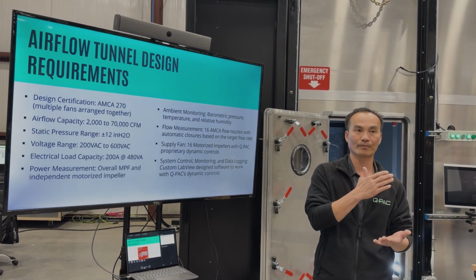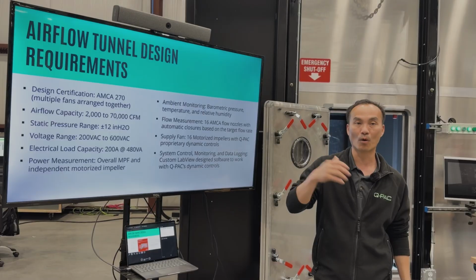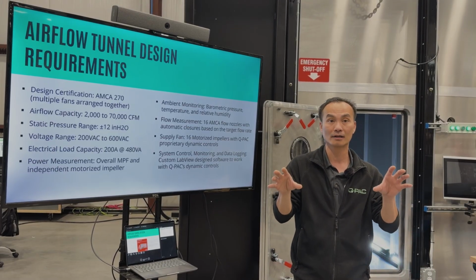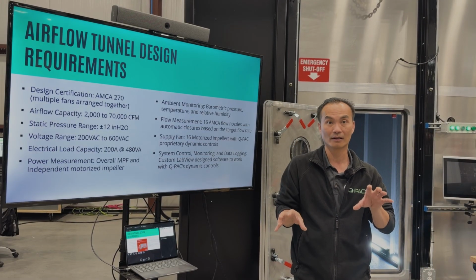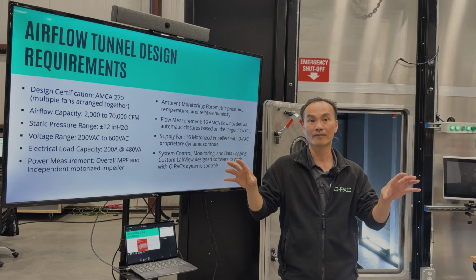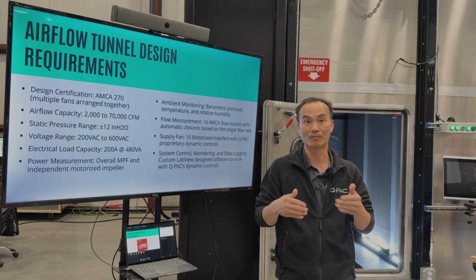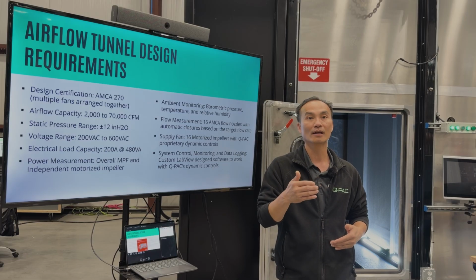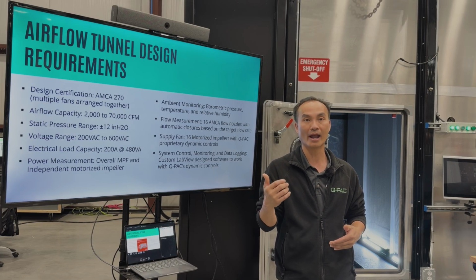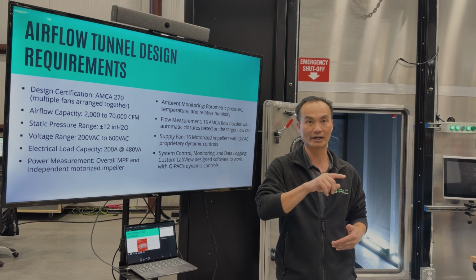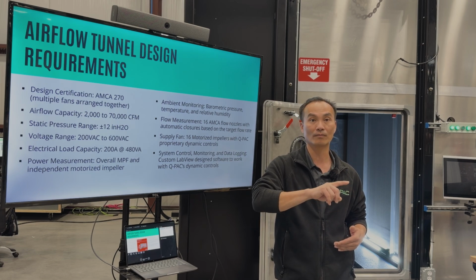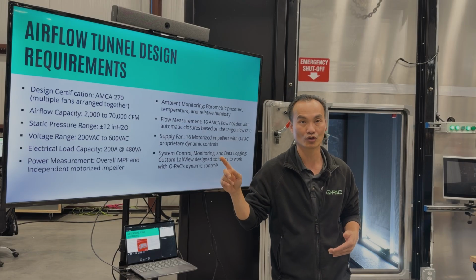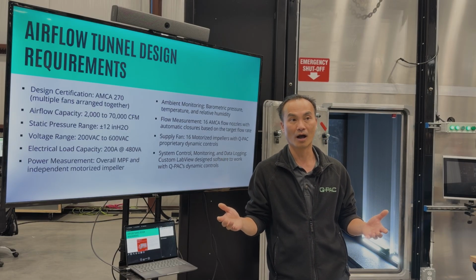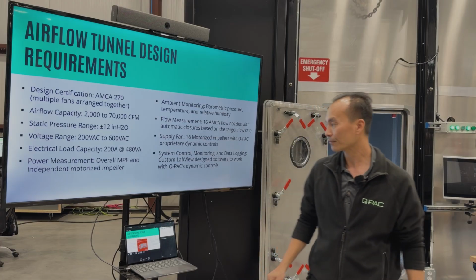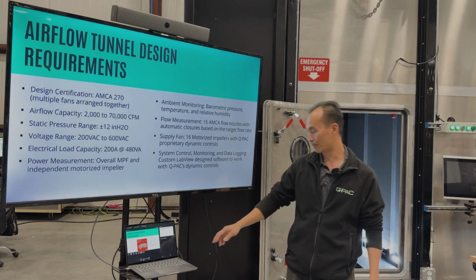Because of the amount of testing required for multiple fans working together, and the product permutations of the fans, there are so many factors that affect the dynamic effect and the performance of the fan. We use the testing combined with software and data in order to extrapolate all the data, to reduce the amount of tests that we have to do in order to cover our whole profile of products. So that is a nutshell of the airflow tunnel and how it's designed.